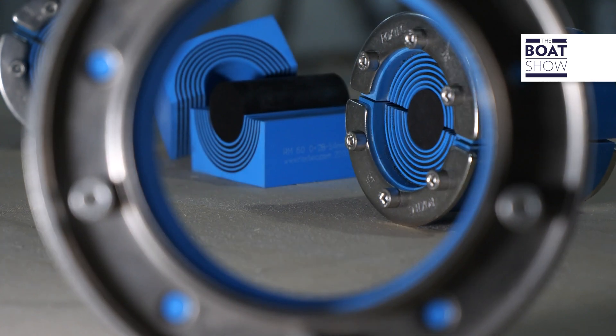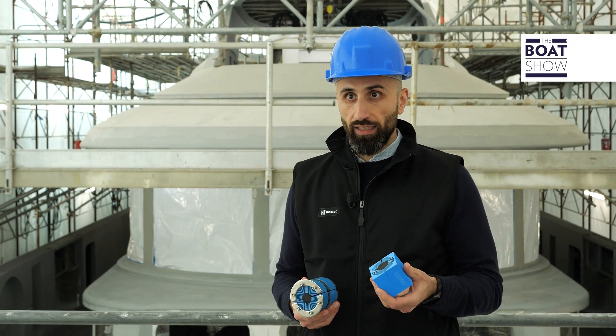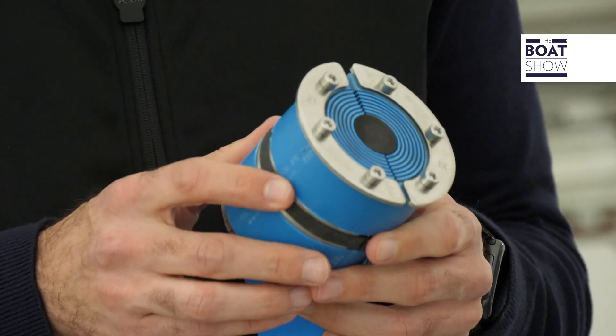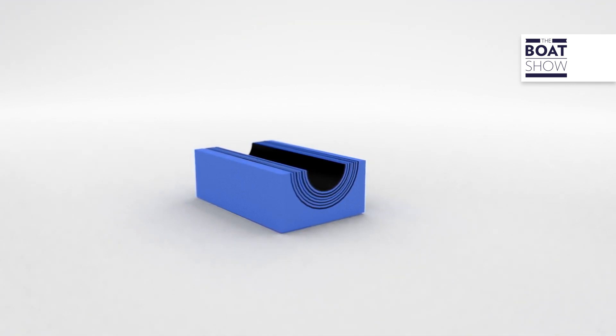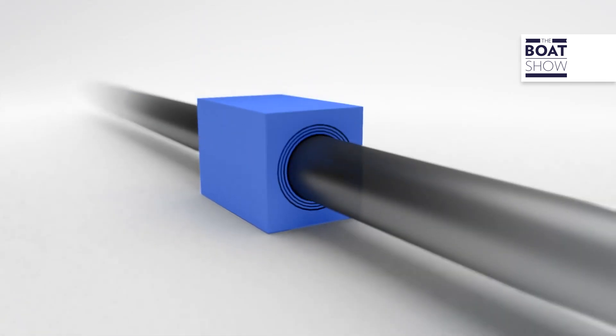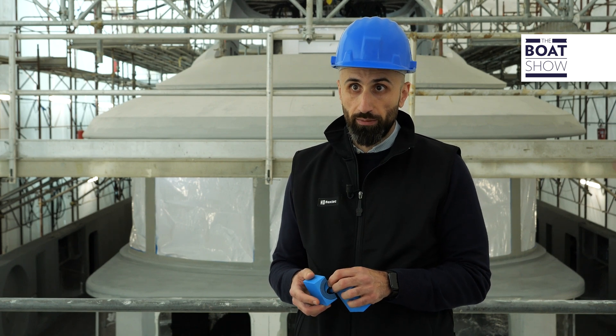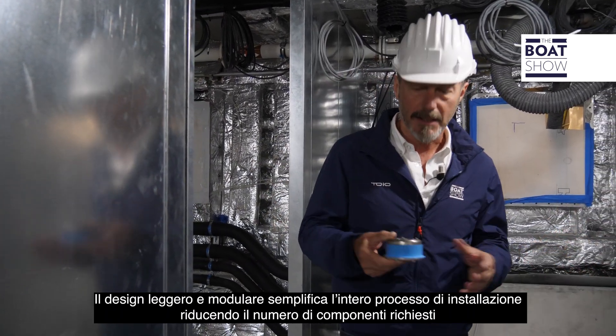Our systems can be made of RM modules like this one, which are inserted inside a rectangular welded S-frame. Metal pipes or cables can pass through them. With circular passages like this one, inserted inside a circular metal sleeve, plastic pipes can be sealed. Thanks to the adaptability of our modules, which can be peeled to match the diameter of the cable or pipe that needs to pass through, we can adapt to various diameters, minimizing the number of components needed on board.